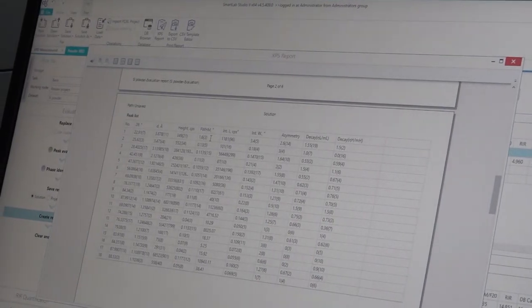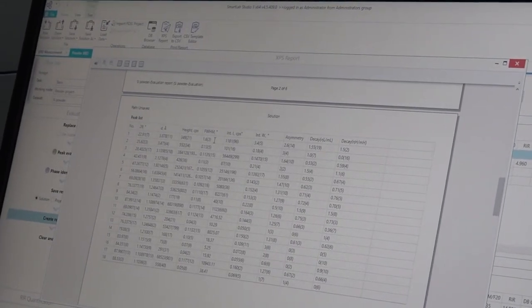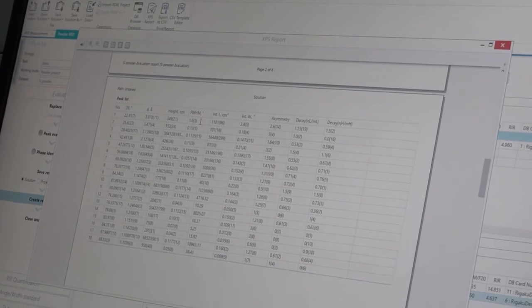I don't know. Why is the instrument showing X-ray on still, even after the analysis is done? No, X-ray is on only. But we finished the measurement. No, the measurement you finished, madam. It just closed the shutter. But before that, the X-ray is on only. Okay, so now the shutter is closed. Yes, as soon as the analysis is done. Yeah, you can see now. See.